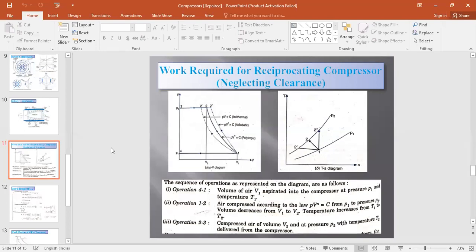If the pressure ratio is more than 1.5, we call it a compressor. Through a compressor we can achieve high pressure air. The function of a fan is to just direct the air with a very negligible pressure increase. A blower provides a slight pressure increase. A compressor can deliver air at much higher pressure ratios.